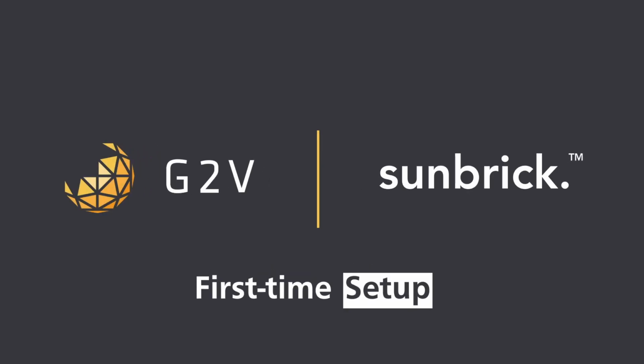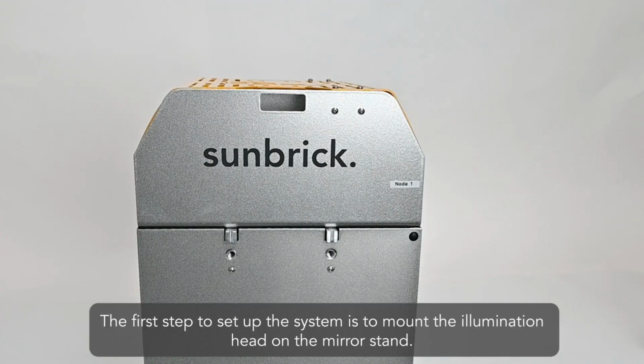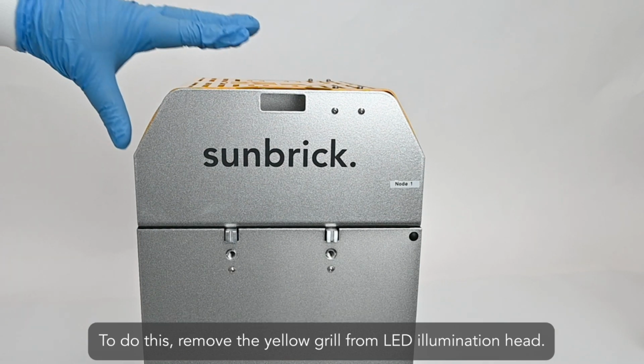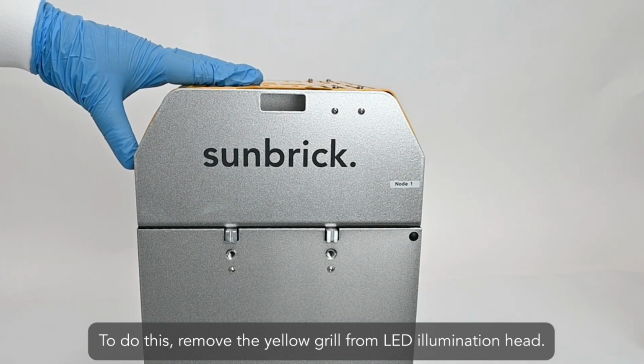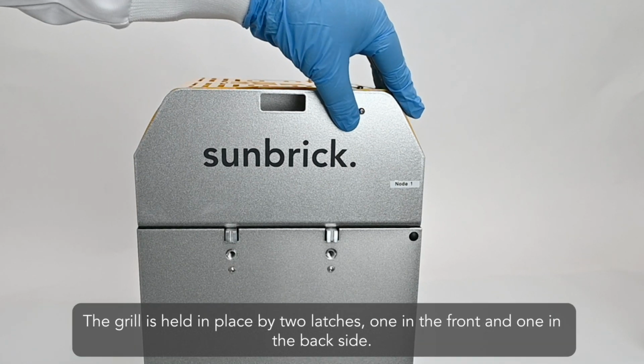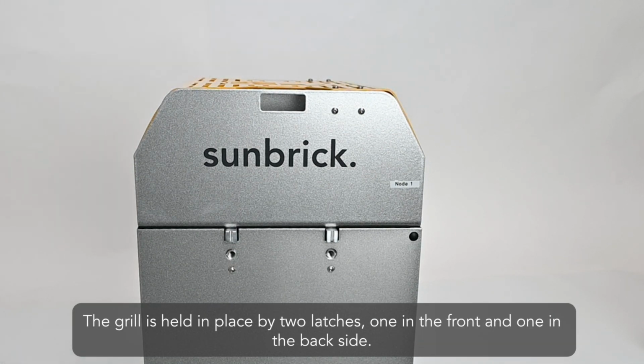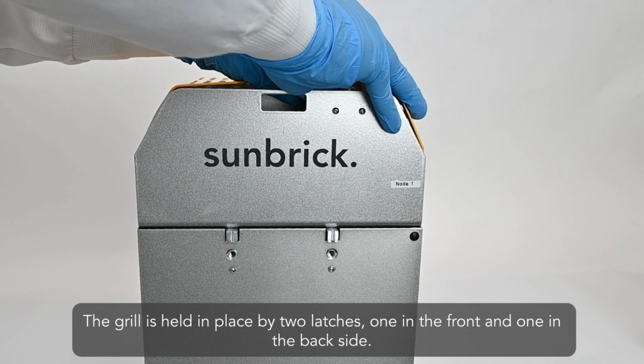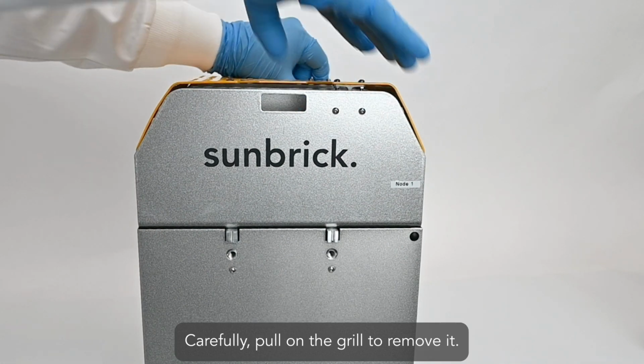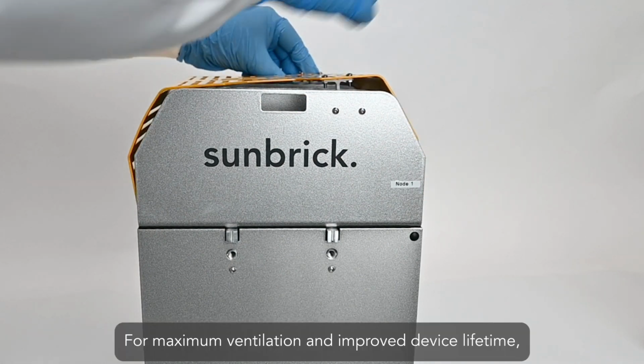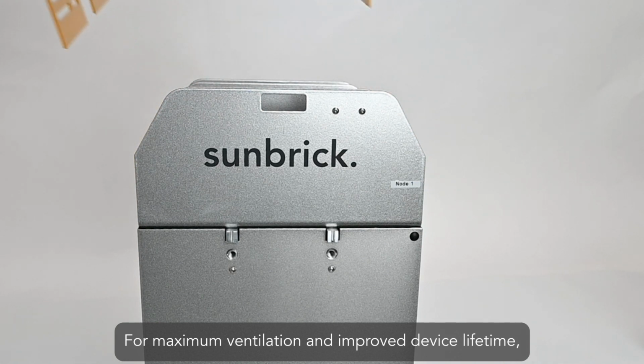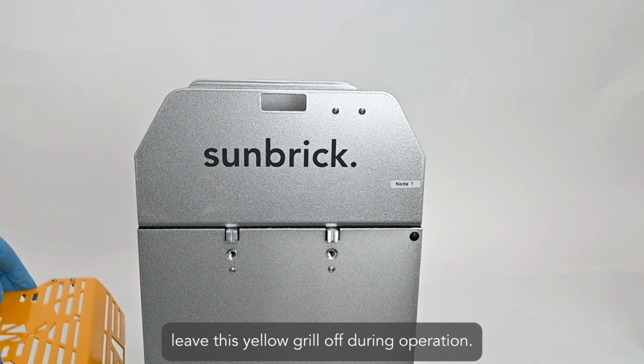First time setup. The first step to set up the system is to mount the illumination head on the mirror stand. To do this, remove the yellow grill from the LED illumination head. The grill is held in place by two latches, one in the front and one in the back side. Carefully pull on the grill to remove it. For maximum ventilation and improved device lifetime, leave this grill off during operation.